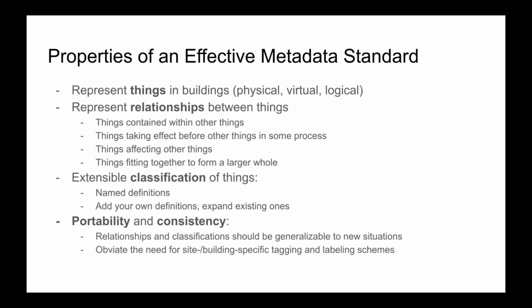We also needed to represent relationships between things - the fact that some things are contained within other things, or some things take effect before other things in a process, such as a valve needing to open before hot water can heat air, or one fan occurring before another. Things affect other things, like a hot water coil heating air, and things fit together to form a larger whole, such as an air handler unit, VAV, dampers, return fans, and exhaust fans all assembled into the HVAC system or air loop.